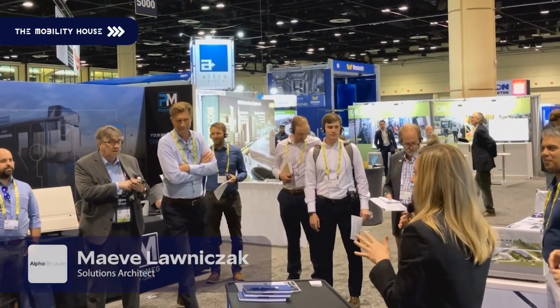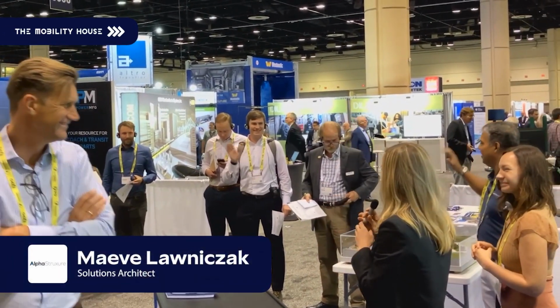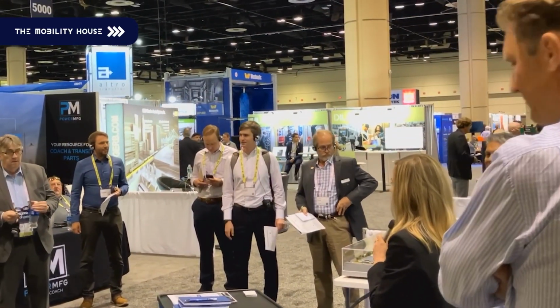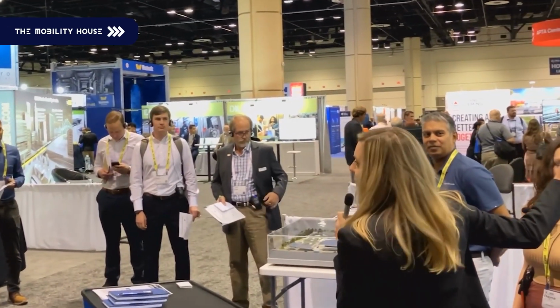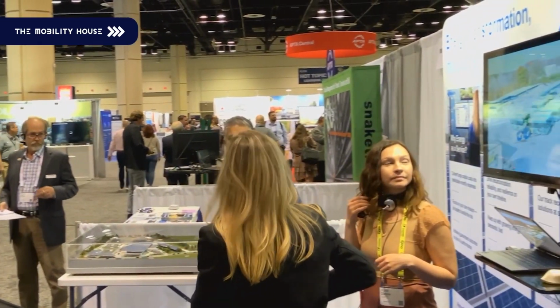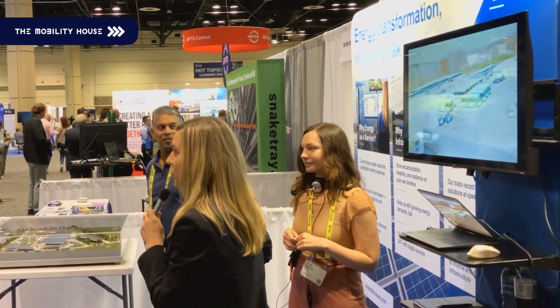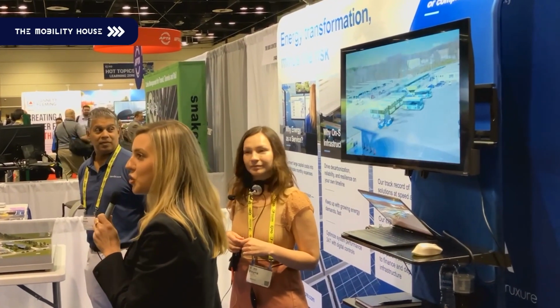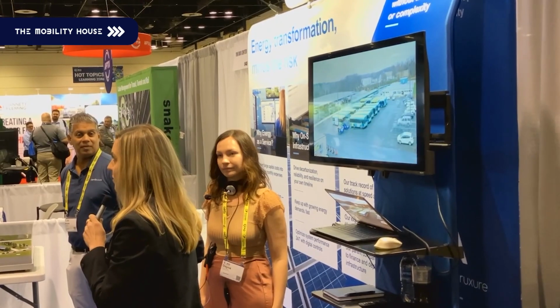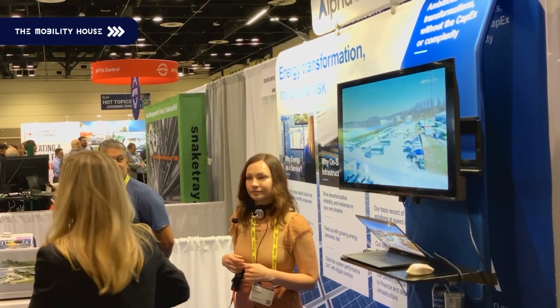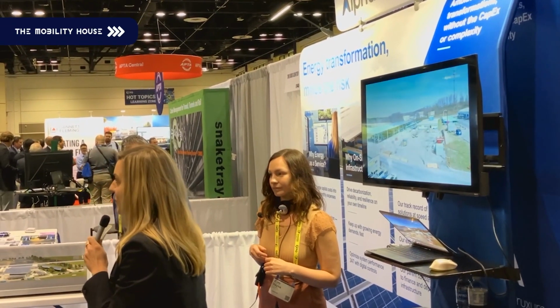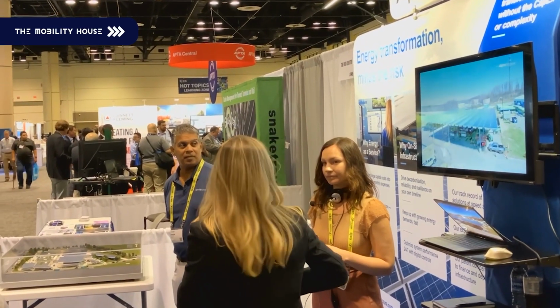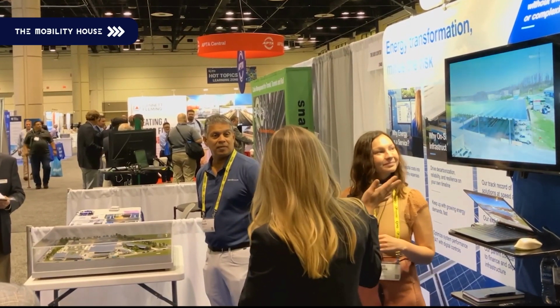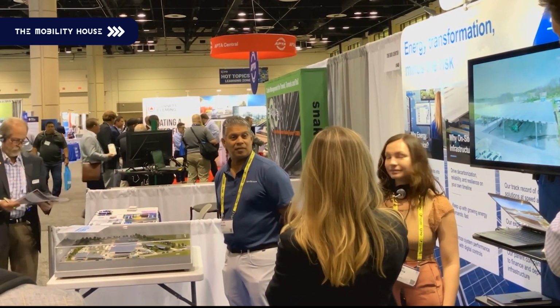There are a few different projects we wanted to talk with you about today. The first is our Brookville Microgrid Bus Depot in Montgomery County, Maryland, shown being constructed on this television behind me. This is a microgrid built for 70 electric buses. It has a 2 megawatt solar array, 1.9 megawatts of natural gas generators convertible to biodiesel or hydrogen, a 1.5 megawatt, 4 megawatt-hour battery energy storage system, and 4.5 megawatts of charging capacity. We constructed this in around a year, and this is a time-lapse video of the site being built over that span.